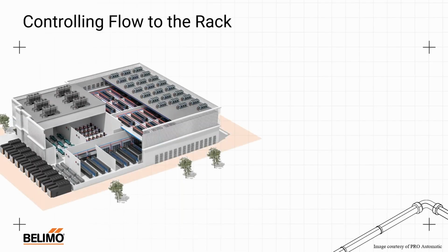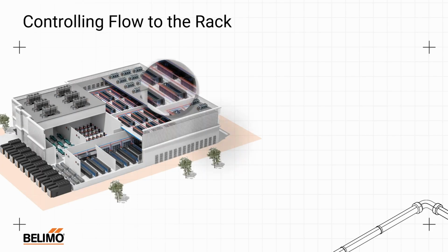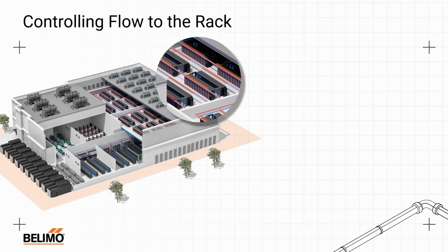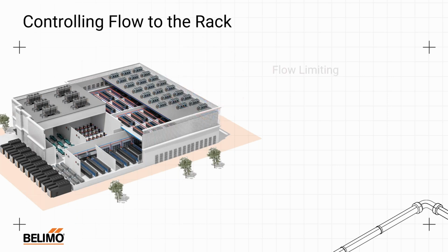Let's talk about controlling flow to the rack, because there's a few options. So we have our data center over here on the left-hand side, and this is the Belimo data center, which has like every form of cooling involved in it. But if we zoom in just over here where we're going to do direct to the chip type cooling, you can see we can have some kind of header with our fluid coming in, and then we'll have some kind of control device that goes directly down to the rack, and we need to control that flow going into the rack. So we have a few options.